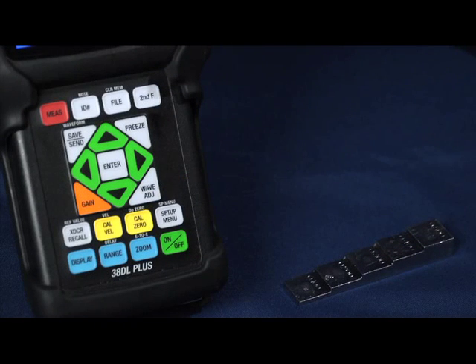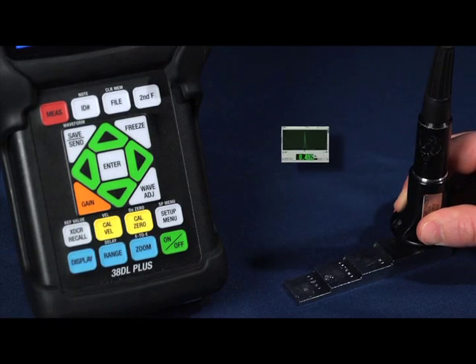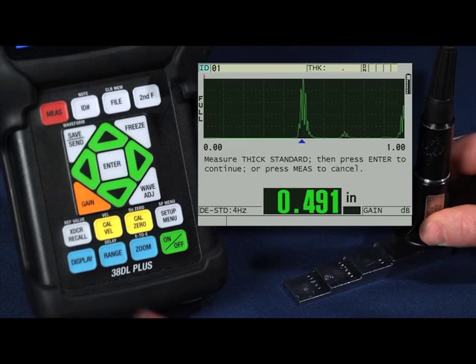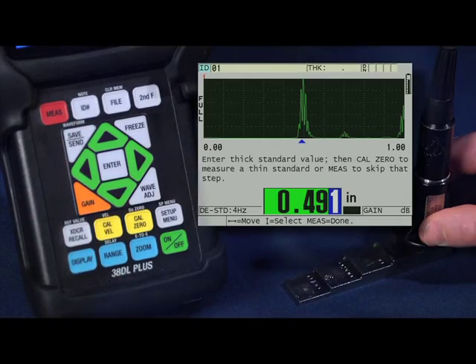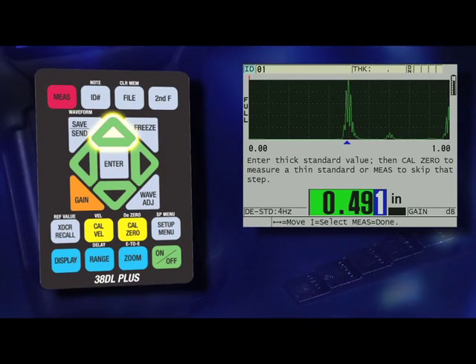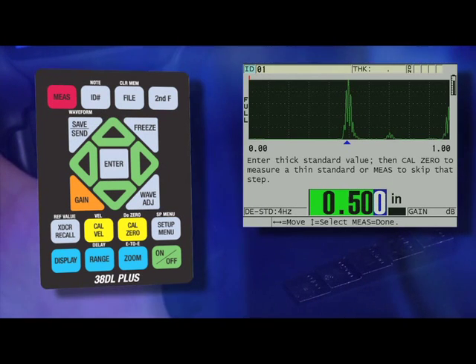Simply couple to your thick standard, in this case the five hundred thousandths step, and press the CAL VEL key. Once we have a steady reading, press the ENTER key. You can now use the right, left, up or down arrow keys to enter in the known thickness value of the standard.